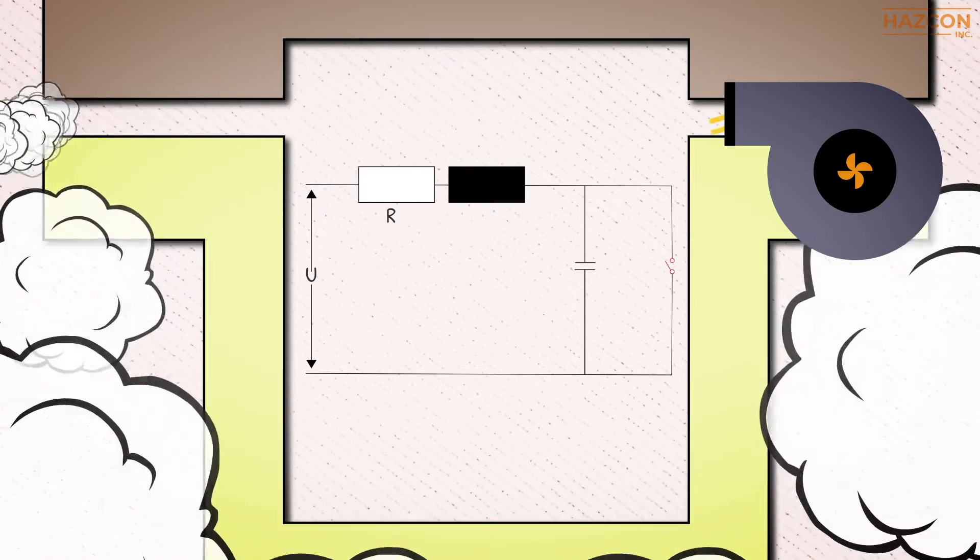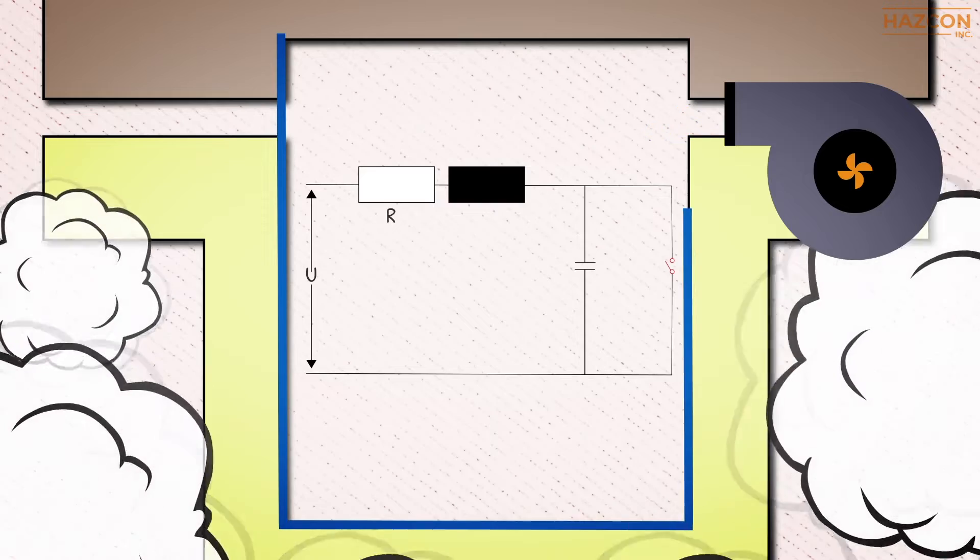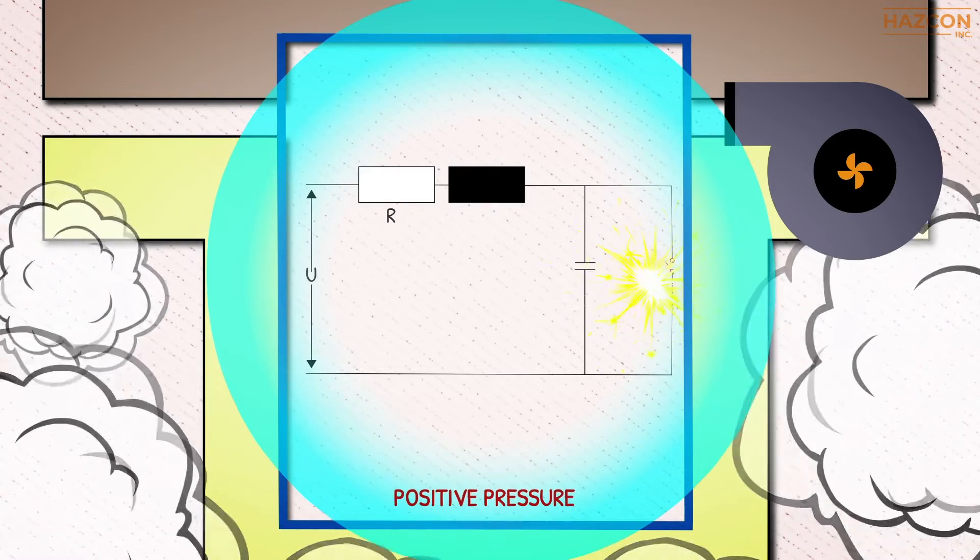Then the atmosphere inside the enclosure is pressurized with a non-explosive gas to achieve and maintain a positive pressure with respect to the atmosphere outside the enclosure. Such positive pressure prevents the ingress of any hazardous substances that exist in the atmosphere surrounding the enclosure.